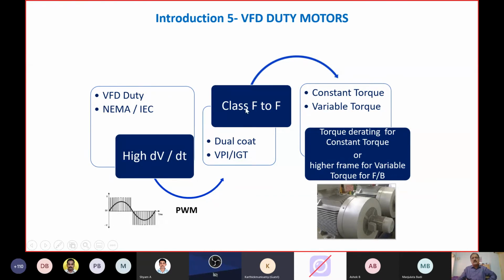Now, the second step is to understand that even after you do this exercise of making the motor qualified for VFD application, the temperature rise of the motor will remain class F. IS 15881, which I introduced to you a few slides back, deals with this topic. Utilizing temperature rise lower, from class F to class B level, will increase the insulation life of the motor. Therefore, whether it is a constant torque application or a variable torque application with VFD, either torque derating has to be applied or a higher frame has to be selected to restrict the temperature rise to class B.